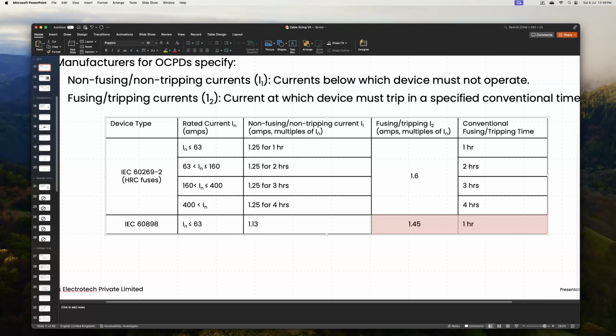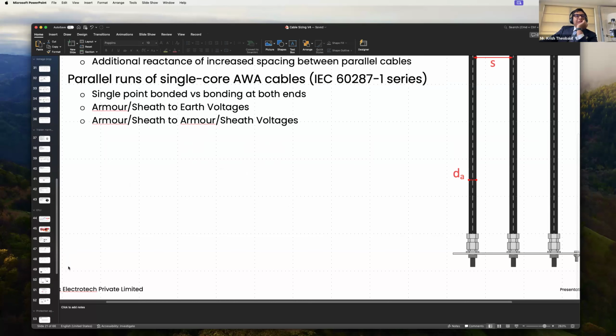That's all, Krish. Almost all the questions. Interesting question, actually. What factor should we consider during low voltage cable fault? What is the effect of temperature? Very interesting question. But as I mentioned earlier, we need to consider maximum operating temperature. So during a fault, we consider the cables are at 70 degrees. There are some countries and some standards that look at different values. They look at conductor resistance at limiting temperature, or at a temperature between limiting temperature and maximum operating temperature. It really depends on the protective device and how quickly it is able to disconnect.